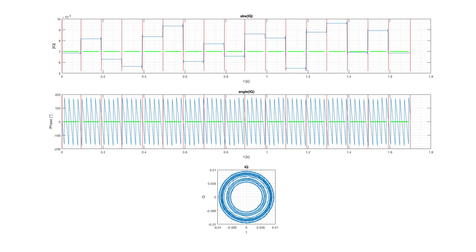In the software, we can see the recorded IQ data over time. The software automatically recognizes that we have switches between the elements, as marked with red lines, and will analyze only the green areas. This leaves a little bit of a guard period around the switches.